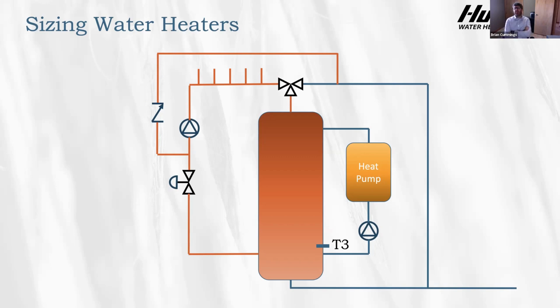What we're doing here is with the heat pump, we're pulling from the bottom of the tank and we're pushing to the top of the tank. If you're using, say, an external kind of semi-instantaneous heater, this would be the way that you do it. And again, it might loop through that. You might do a 20-degree delta across the heat pump or the heater in most cases. And so it has this kind of multi-pass thing. Again, what's going to happen here is the recirc water could be pulled into the heat pump. You get quick changes of the water temperature there, which we don't want to have happen. And this is going to, just overall not operate to the optimum way that heat pumps can.